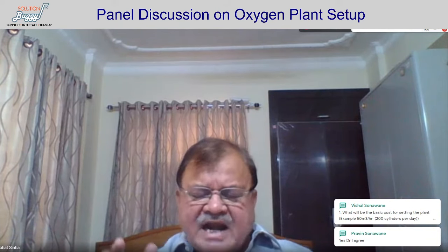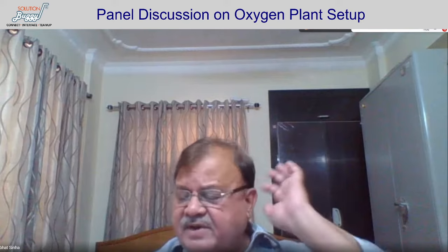And of course, liquid oxygen. Whenever there is a liquid oxygen flow, there should be a safety valve provision, because the trapped liquid oxygen has a tremendous volumetric expansion, and that can damage the pipeline.